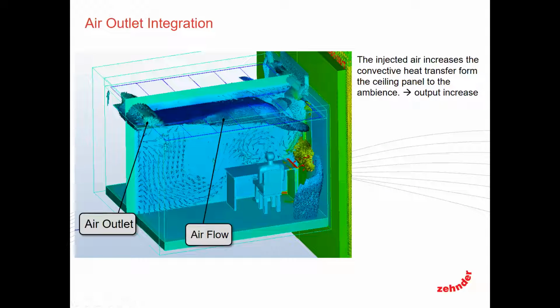Manufacturers can tell you what these values are depending on feet per second, or velocity of the air. They'd be able to give you the percentage increase over the base, meaning the base output capacity that's generated from the standard. We can tell you what those are going to be, so you'll have a general idea. Moving through your design, you'll have an idea of what that safety factor looks like. I also have seen over the years, as you become more experienced with radiant systems and you've done a number of them, engineers actually reduce the number of active panels in the space using these factors, which then, of course, reduces your overall installation cost too.